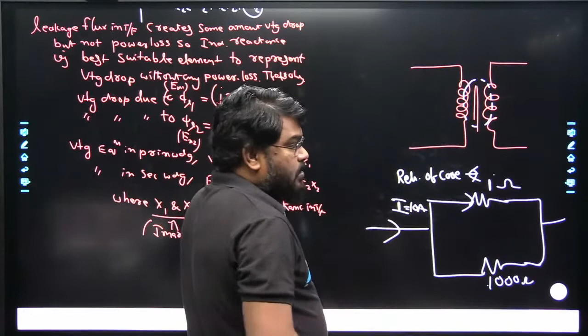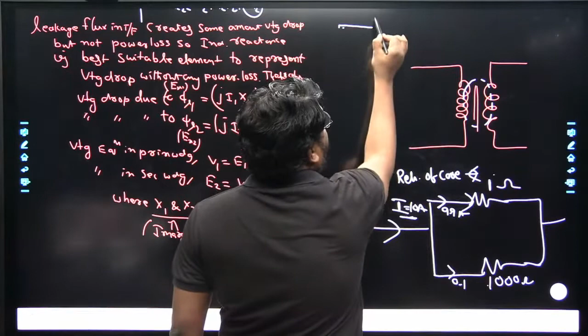No, not at all. See here, Shrutika, I know your question. The leakage flux comes into the picture under loaded condition. Under no load condition, there is also a small amount of leakage flux practically, but it is neglected, it is a very small value. The magnetizing current is only 4 to 6% of the rated current, so that leakage flux is negligible, but the flux due to the rated current is very high. That's why we cannot neglect this flux.